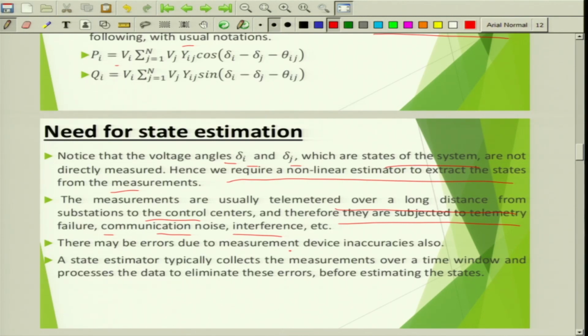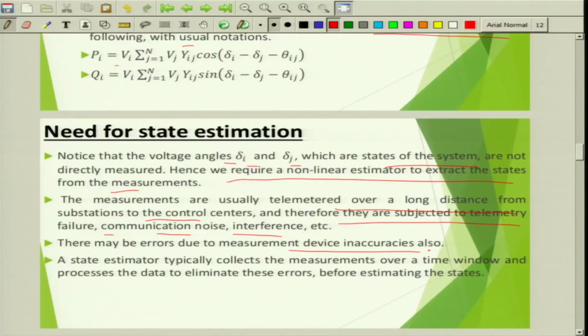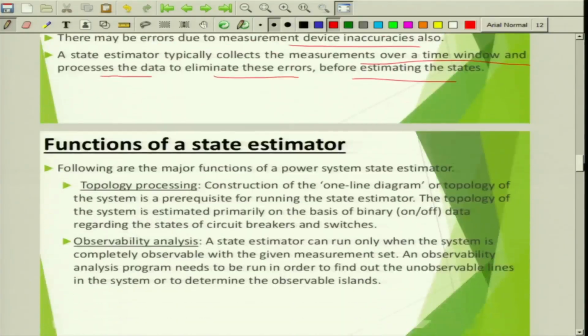There may be errors due to measurement device inaccuracies also. Sometimes a device giving data may start malfunctioning, so that is another reason why you need state estimation, to judiciously identify which data is correct and which is incorrect. A state estimator typically collects measurements over a time window and processes the data to eliminate these errors before estimating the states.